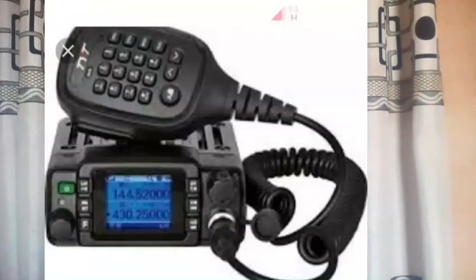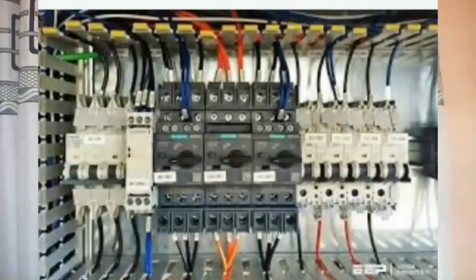So what is the function of that 50-volt battery bank in your station? The function in the station is for communication purposes. Your telephoning, your radios, all these use the 50-volt battery banks. And sometimes, not always, but in some other designs, the remote control circuits of a station have contactors, and some of the contactors are being supplied with the 50 volt.